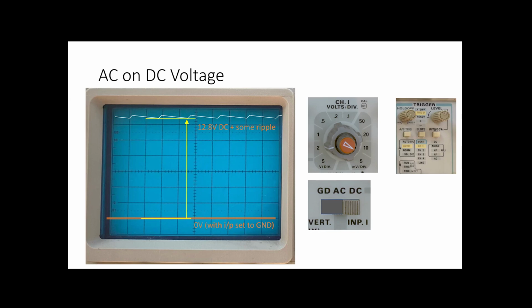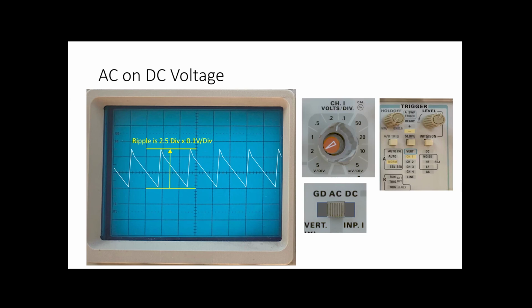And at that point, I turn the volts per division knob around to 0.1. I turn the triggering to normal, and using the level, I adjust the level till I've caught the signal. And once I've caught it, I can read off, I reckon that's 2.5 divisions at 0.1 volt per division is 0.25 volts. So I've got 12.8 volts plus 0.25 volts of ripple.